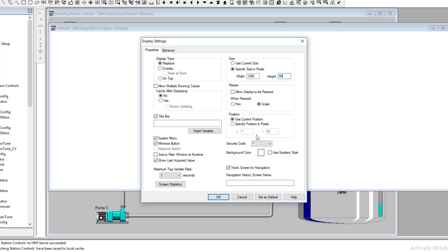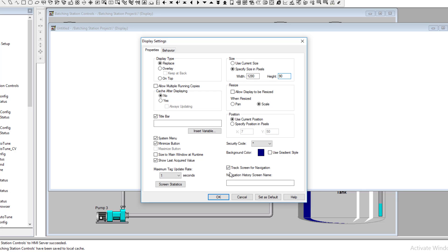The height is based on how tall you want the header. We'll change the background color, keep navigation tracking on, and change the update speed to maybe half a second. We want to turn off the system menu and the minimize menu because we don't want to give the operator the ability to get off of the screen — we want complete control over the HMI. We'll size to main window at runtime.